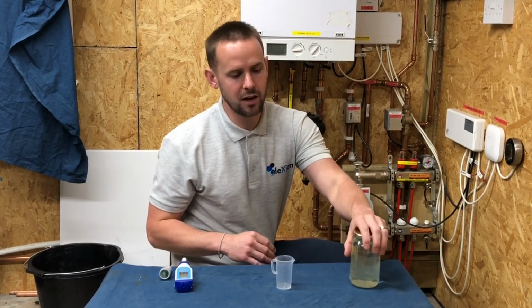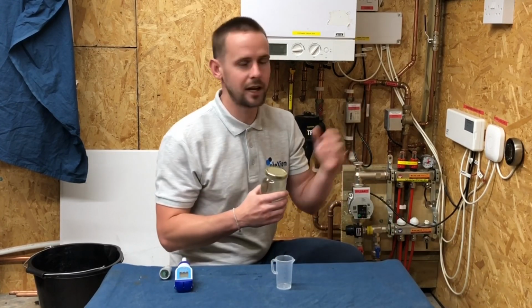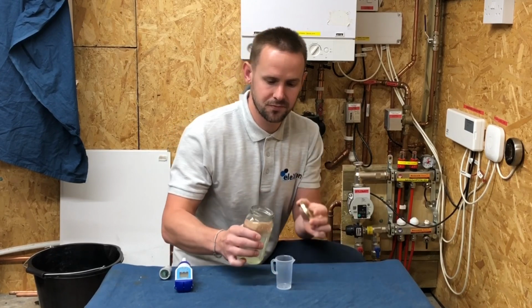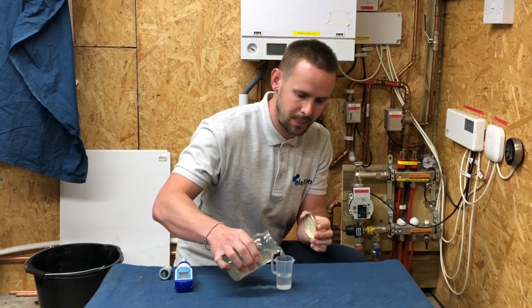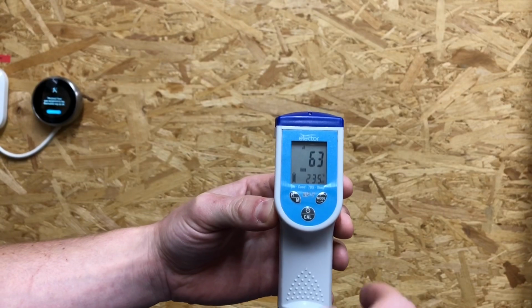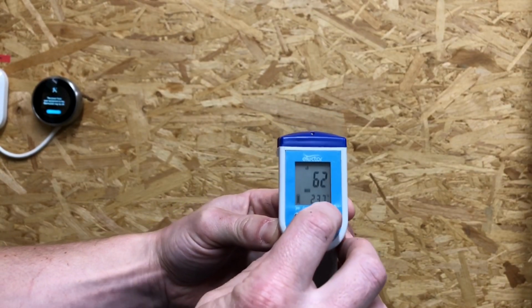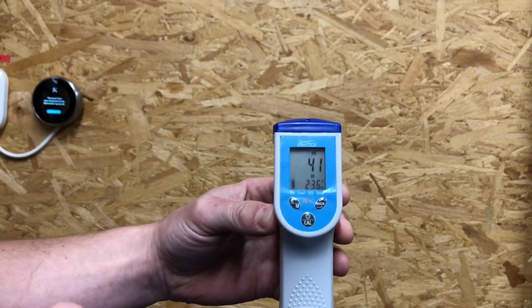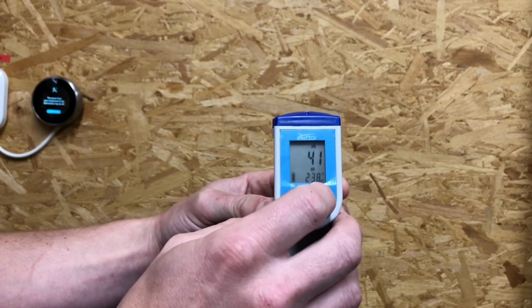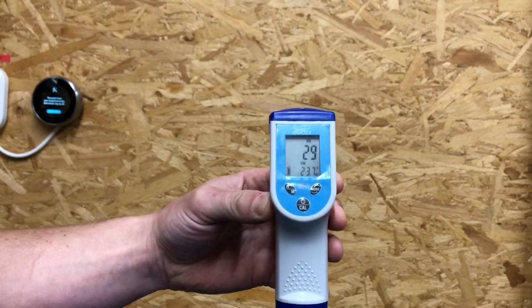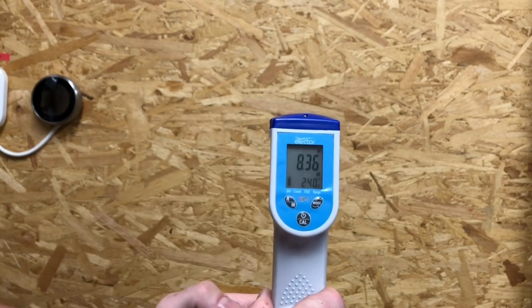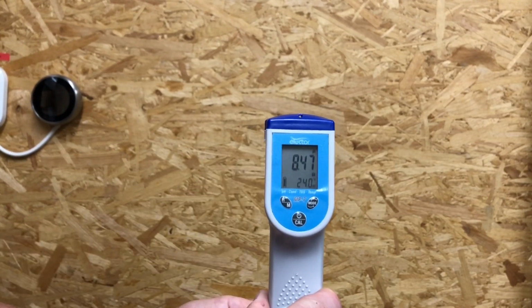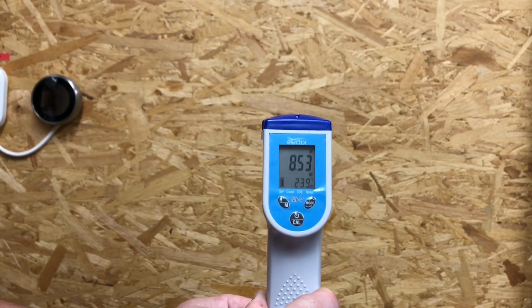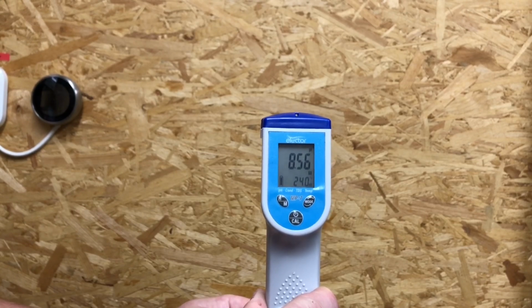Right, what we're going to do now is test the system water from Alan's system. Our conductivity now is 63 microsiemens. Our TDS has dropped to 41. And our salts are at 29. So we're now measuring the pH, and our pH is about 8.5, 8.6 again.